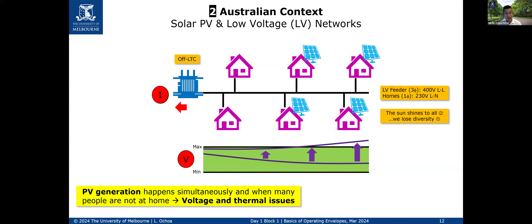Reverse power flows that our assets can generally handle, but if there are a lot, we end up with higher voltages and much higher currents — so much that voltages can go beyond the upper statutory limit, which here in Australia is 253 volts. With a lot of reverse power flows, you can also have power flows that exceed the rated capacity of your conductors or transformers. These are the voltage and thermal issues.